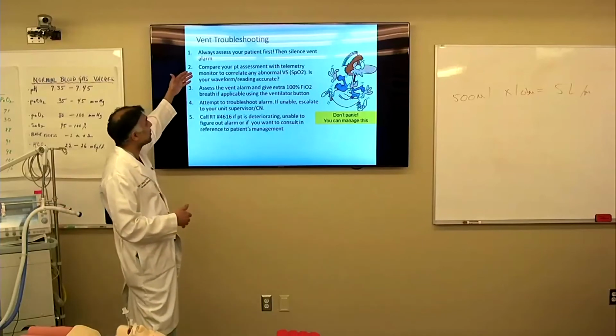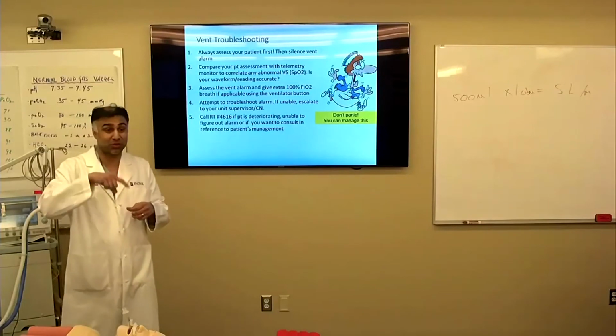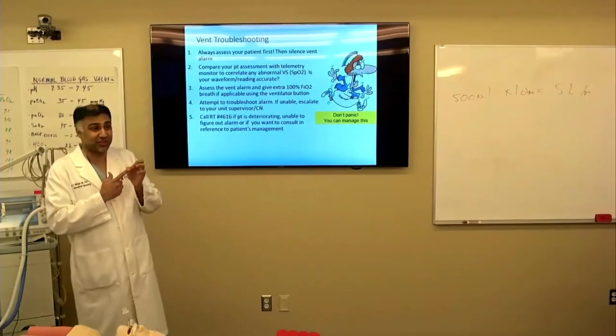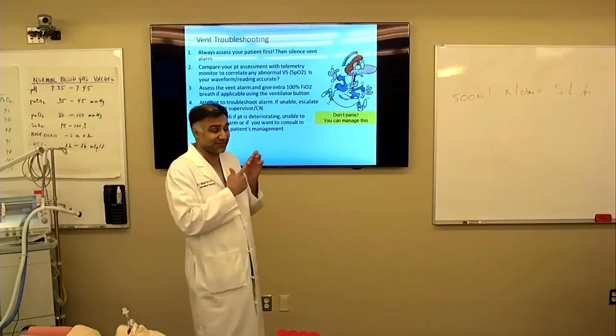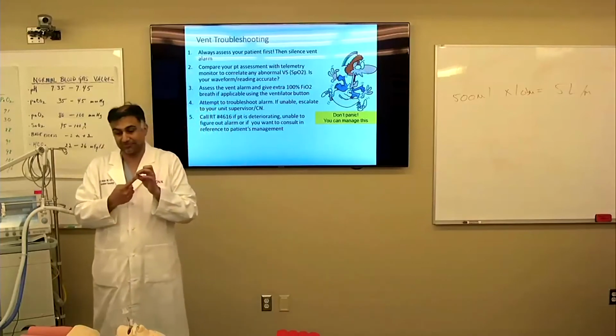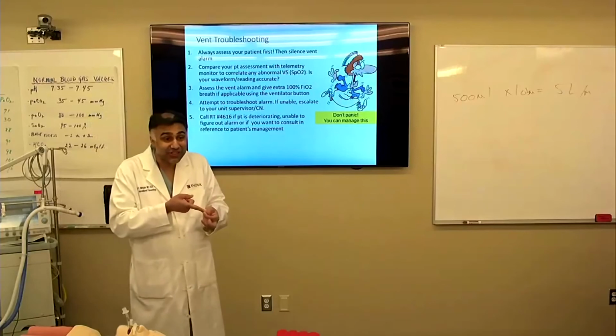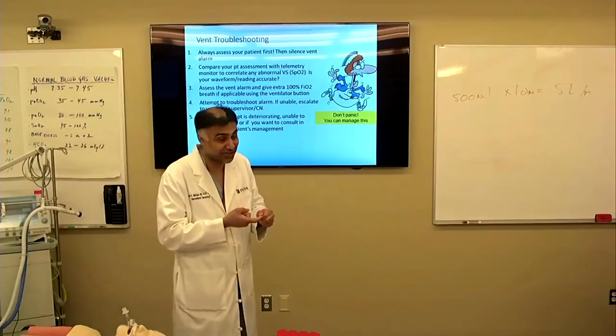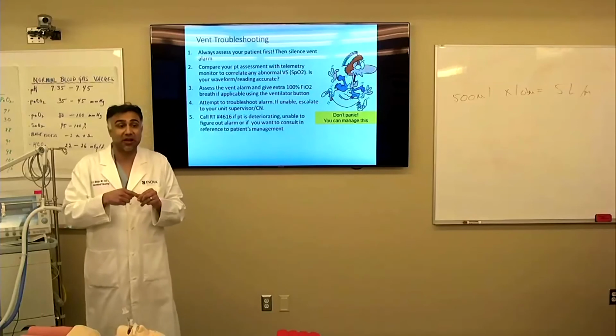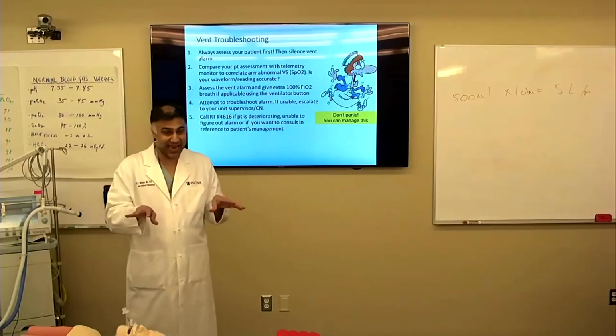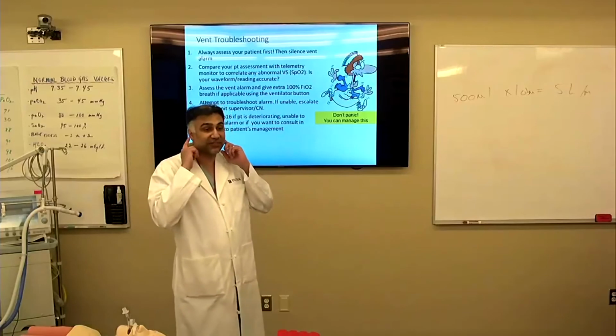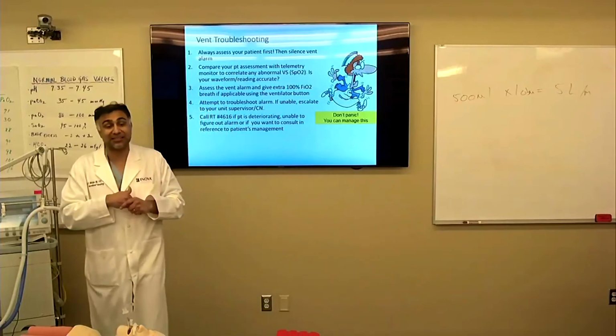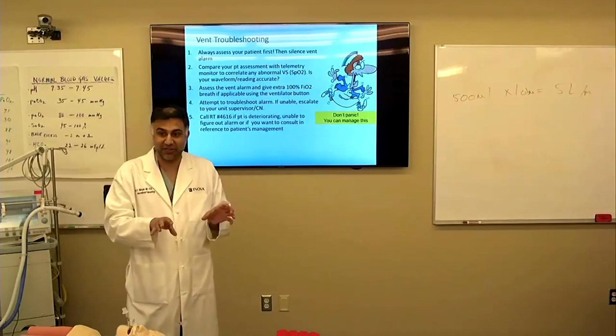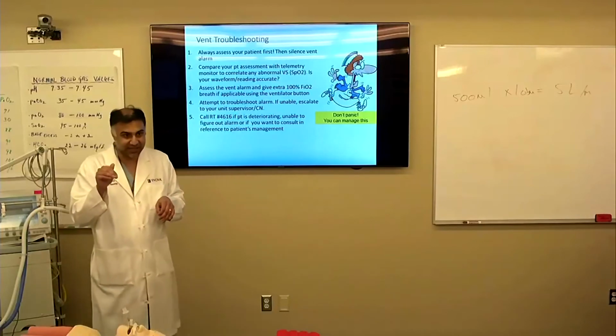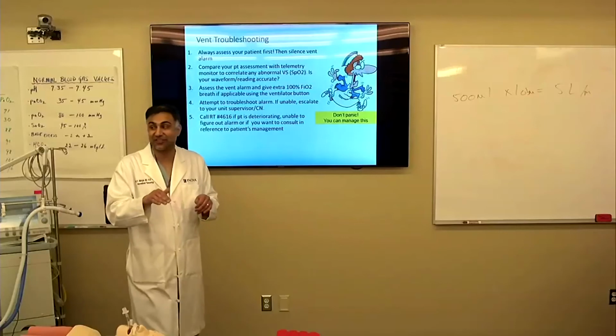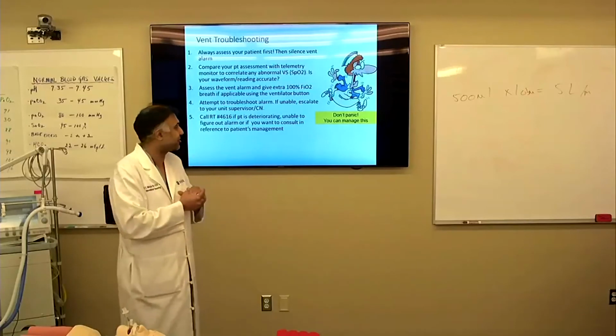The second thing is when you look at an SpO2, when we look at the actual waveform, it really is just looking at oxygenation and saturation by infrared light on your finger. Some people have cold digits. Some people have nail polish on. If you don't have a good wave, it's garbage in, garbage out, it's not an accurate sat. You might have to look at a different spot, on the ears or the forehead. One thing is you can't fake good when it comes to saturation. You can't get to 100% if it's less than 100%. So if it's low, you worry that it might be the wrong saturation.